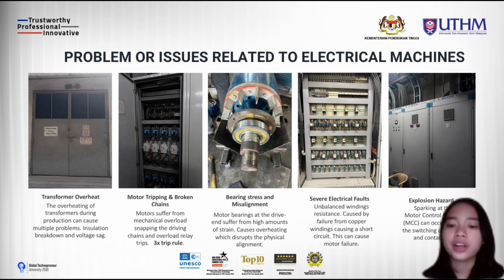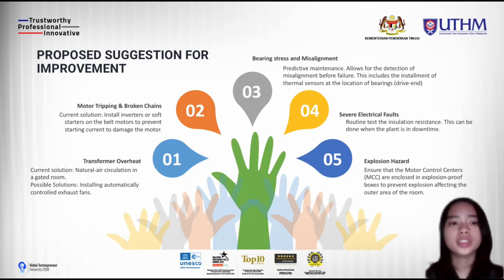The fourth is severe electrical faults due to unbalanced winding resistance. This is caused by failure of the copper windings, causing a short circuit, and motor failure can occur because of this. The fifth and final one is explosion hazard, which can occur specifically in the MCC or motor control system. This occurs because of the switching of starters and contactors.